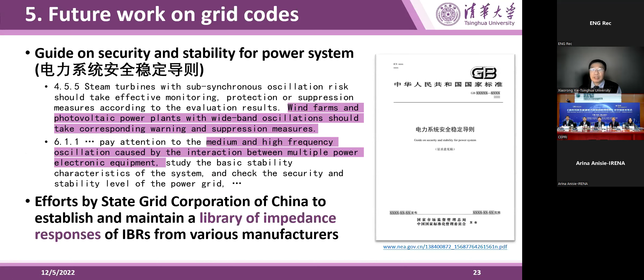Globally, there are efforts by utilities and system operators to accommodate SSI stability requirements into grid codes. Meanwhile, many working groups or task forces have done work toward this purpose. For instance, the IEEE, IEC, and CEPRI work groups and task forces associated with SSCI and SSO, in which many researchers, including myself, have participated over the past years. However, collaborative efforts are needed to establish grid codes, standards, specifications, and guidelines. This is very important because manufacturers of IBRs are international vendors, and unified interfaces are required to connect their products to different grids.